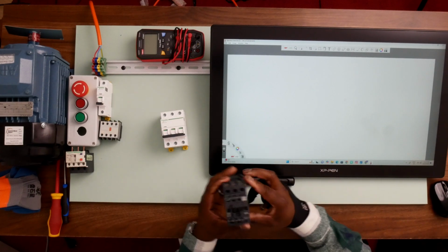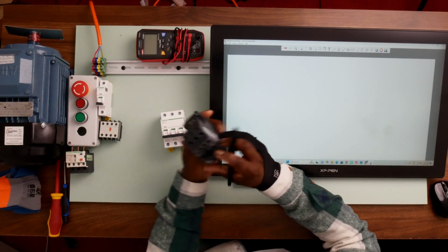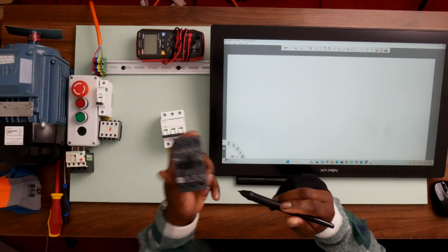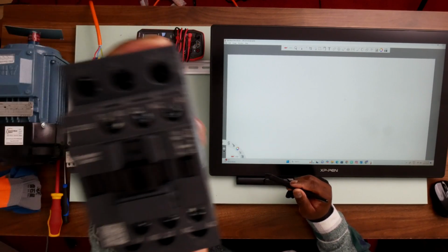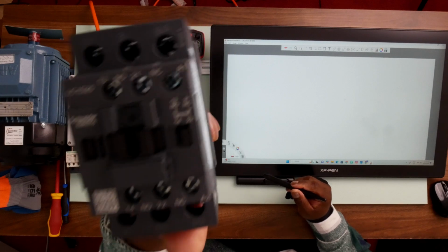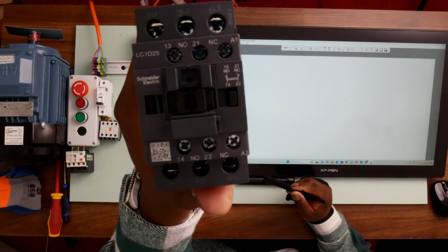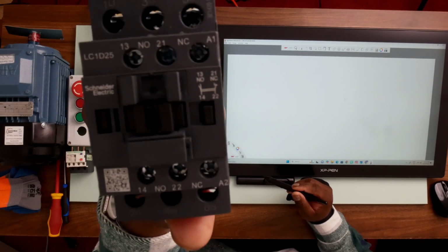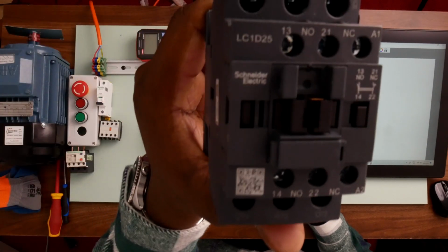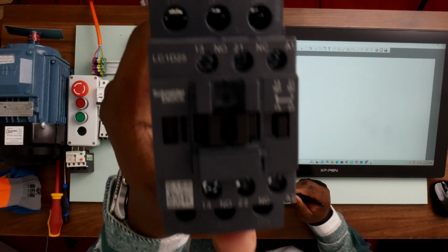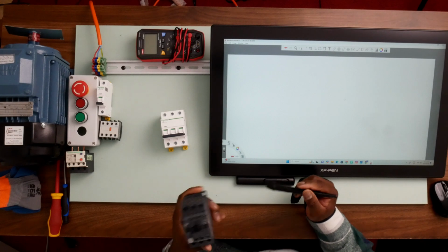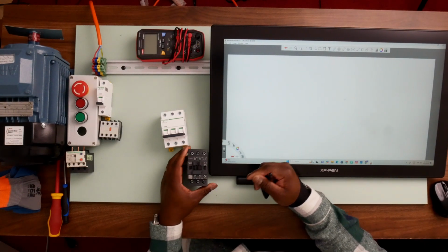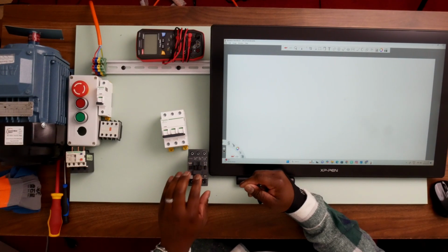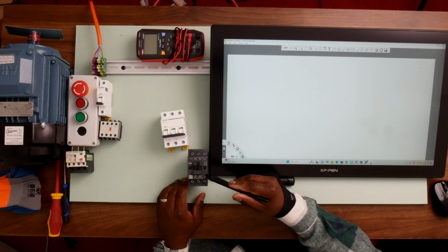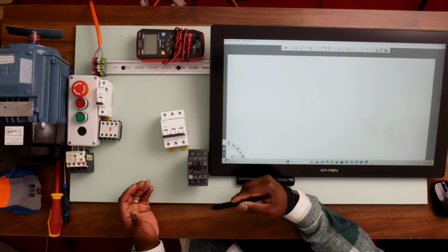So this is a contactor. This contactor that I have here already has built-in contacts that we need for our control circuit. These are built in, which is 13 and 14. They are built onto the contactor here, as you can see, 13 and 14.